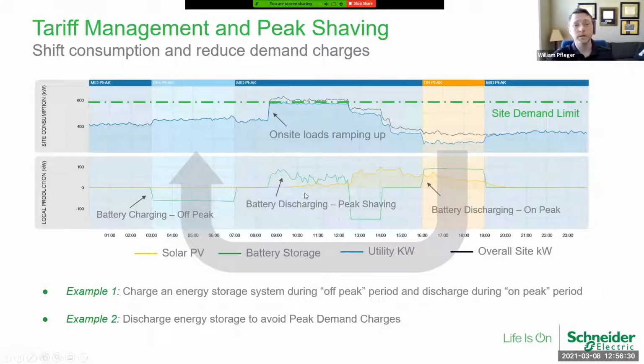On this day it was a little cloudy, so the solar system had not produced a lot of energy yet. The system recognized that and said, okay, I need to discharge the battery to maintain below my demand charge threshold. That's exactly what you see here with this squiggly line, and you see the difference between the predicted site demand above 800 and where it held it below the 800 demand charge limit.